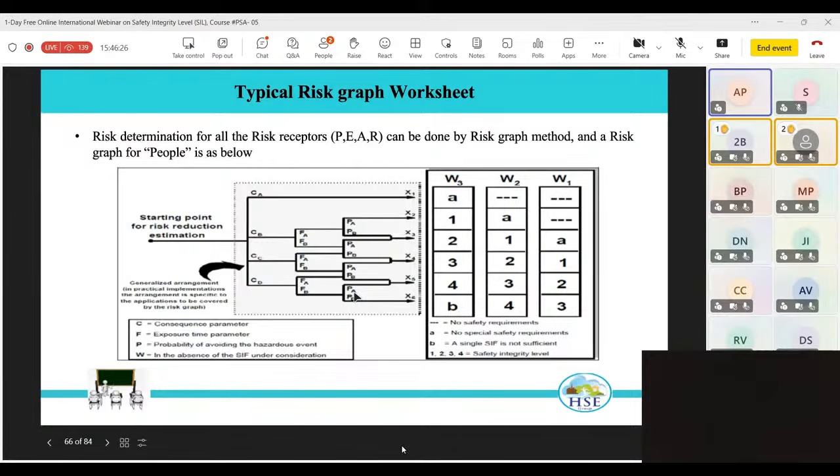And with that, if it is about 5 years ago, this SIL2 was good enough, but nowadays people would like to really design that particular safety instrumented function. That means we'll have to select a proper transmitter, a proper valve, and all these put together should give that risk reduction factor. That is not possible in this case. They will just say that this is a SIL2 loop. And if somebody questions how do you calculate the RRF, you will not be able to do that in case of this graph.